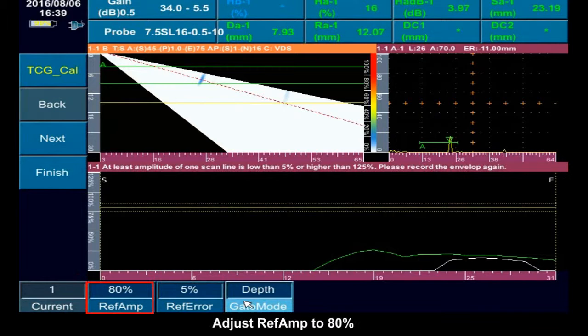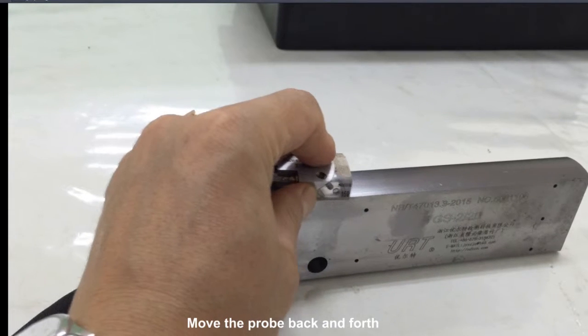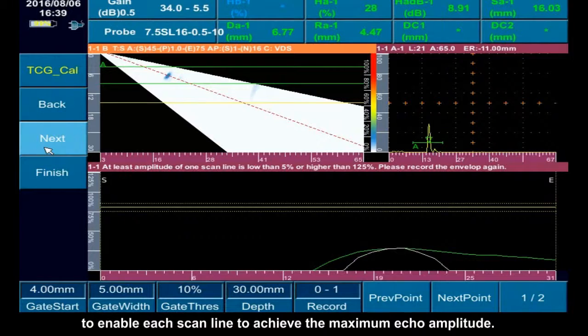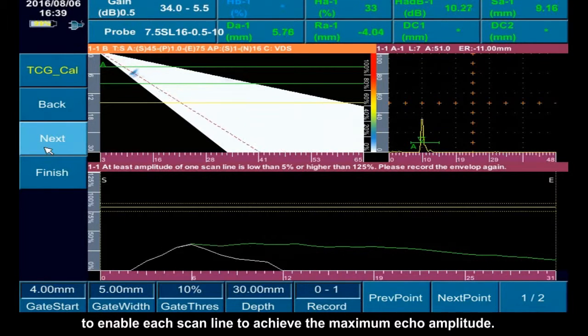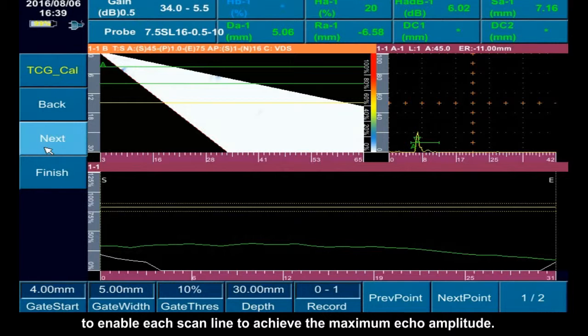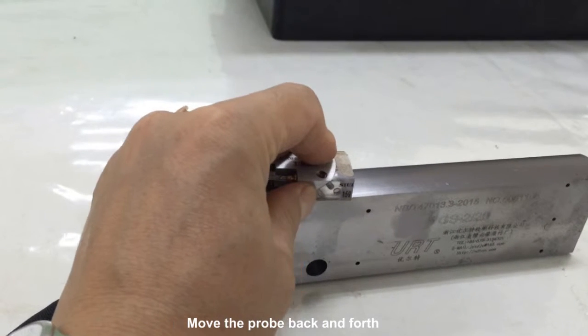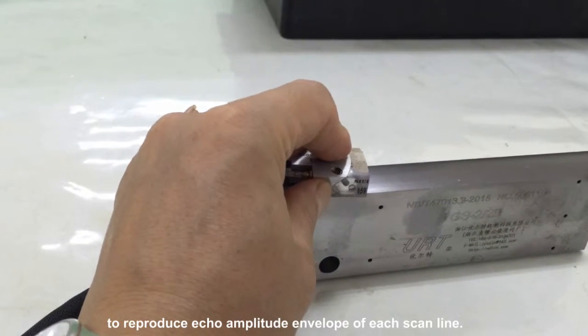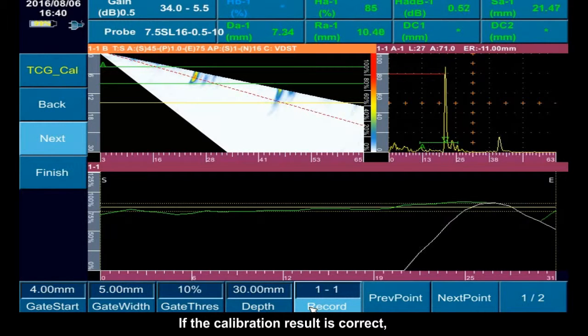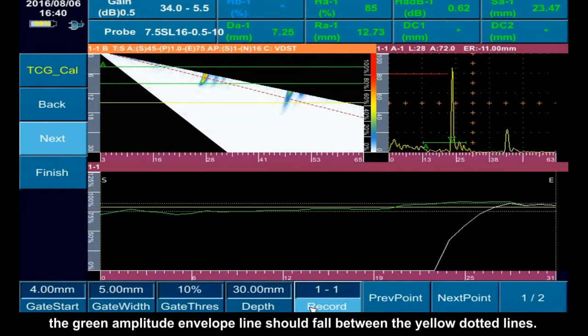TCG calibration. Adjust reference amplitude to 80% and reference error to 5%. Gain mode to depth. Press Next. Move the probe back and forth to make each scan line reach the maximum echo amplitude. Press Record, and the record menu displays 1-1. Move the probe back and forth to reproduce the echo amplitude envelope of each scan line. If the calibration result is correct, the green amplitude envelope line should fall between the yellow dotted lines.